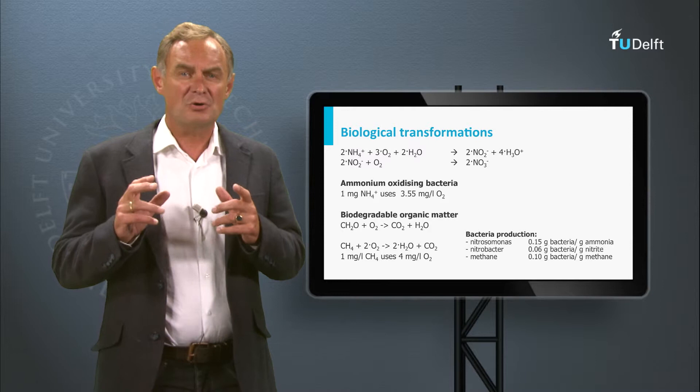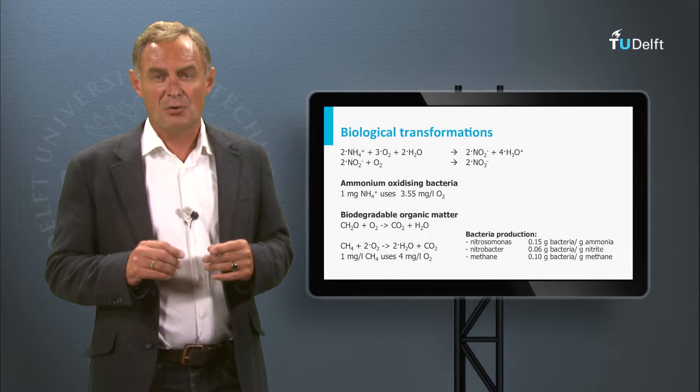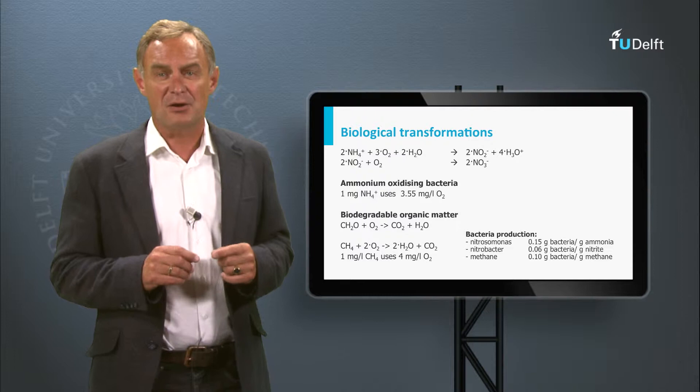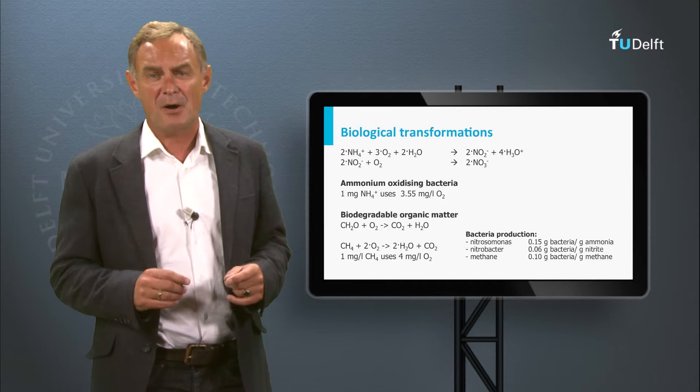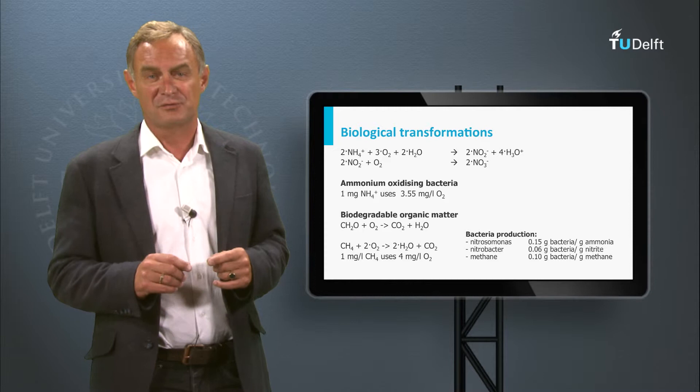Oxidation requires oxygen present in the water. When too many of these compounds are present, depletion of oxygen can occur. In practice, the presence of ammonia can result in unwanted anaerobic conditions in the filter bed, since it consumes about 3.5 mg per liter of oxygen, while the maximum saturation concentration of oxygen — depending on temperature — is about 10 mg per liter.